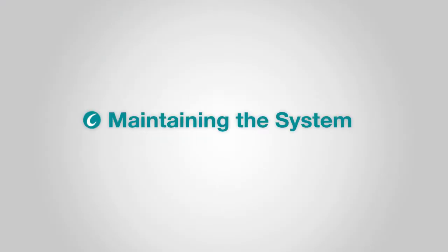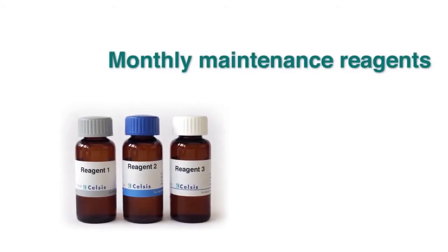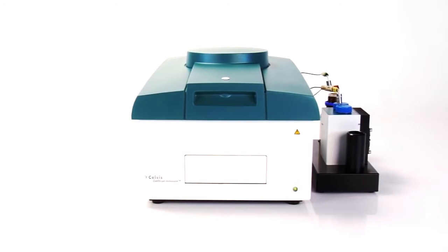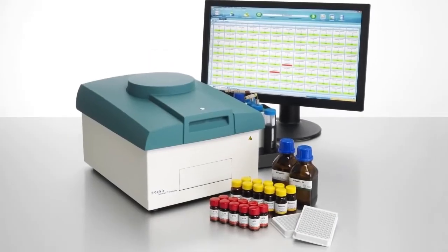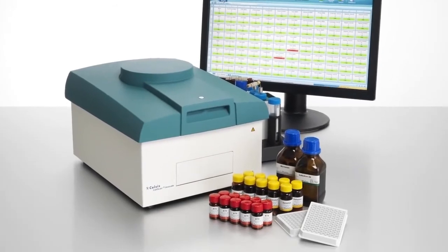To keep your Celsis Innovate in top condition, run the monthly three-hour maintenance and cleaning protocol. In addition, an annual preventative maintenance check includes a thorough cleaning and calibration. These simple steps will ensure years of dependable use with maximum uptime.